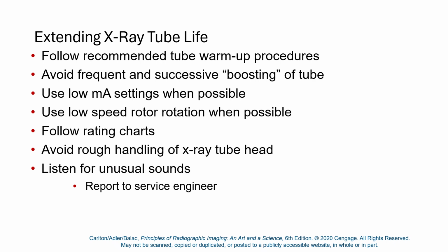damage an anode, you can crack an anode by heat shocking it. You might have noticed the phenomenon of heat shock if you've ever worked with cheap bakeware and you immediately put it into the sink after it's been in the oven. It goes from extremely hot to extremely cold really fast, and your bakeware shatters as soon as the cold water hits it. Okay.